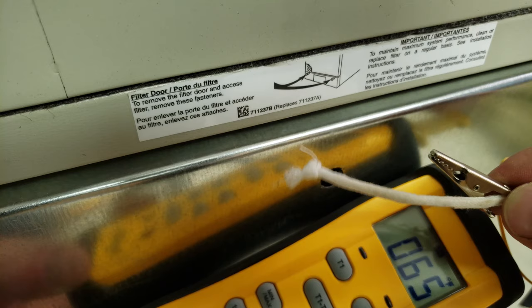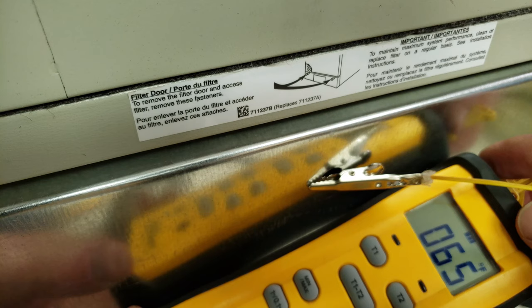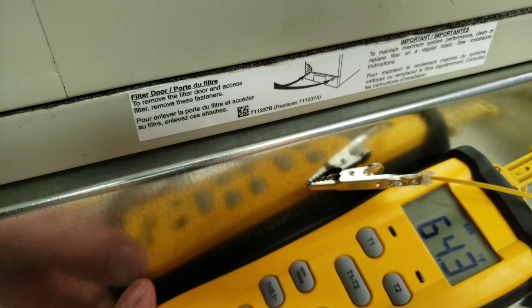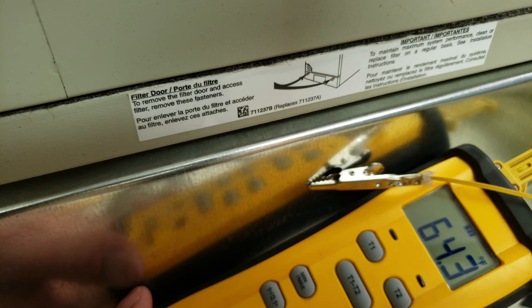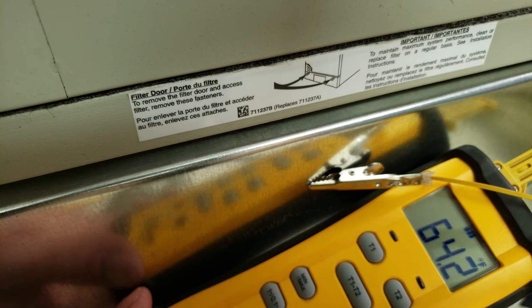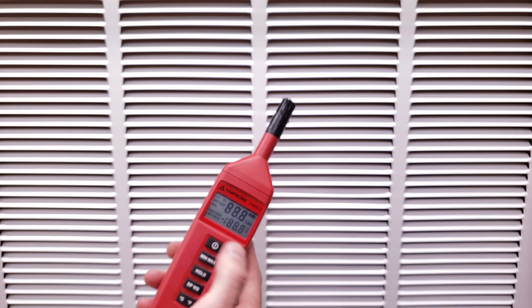Here's our temp reader with our K-Type bead temp sensor with a wet sock over it. I did have this in the duct a few seconds ago, so it should be pretty close to what it's supposed to be. Right about 64.3, but you would normally leave this in the duct for about two minutes or so, but you don't want to dry out the sock either. 64.1.